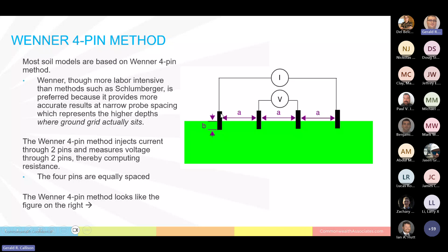So individual Wenner 4-pin readings will be taken at progressively increasing horizontal A spacings. Now, the key is that these A spacings resemble resistivity up to that depth. For example, an A spacing of 2 feet represents resistivity down to 2 feet, whereas an A spacing of 200 feet represents resistivity down to 200 feet.